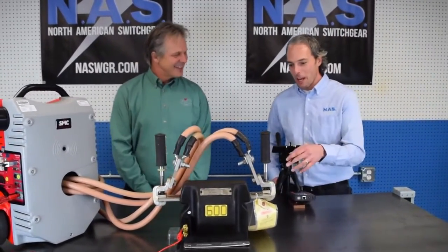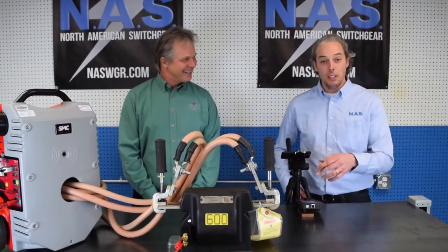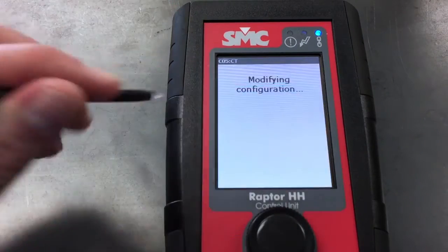Thank you very much. What we have here is an ABB CT — it's a 600 to 5 ratio, and I want to check the polarity of it and also check the ratios.